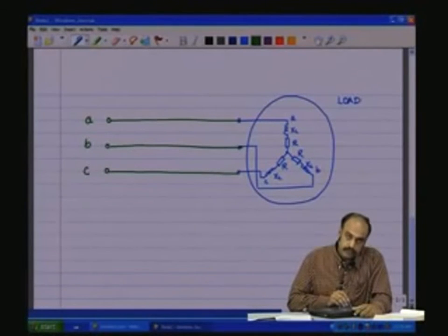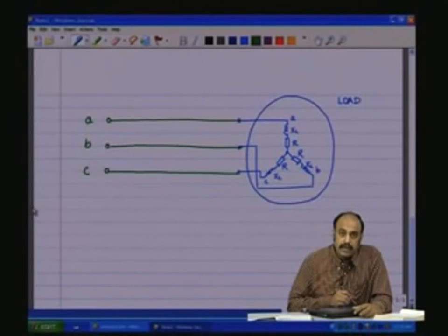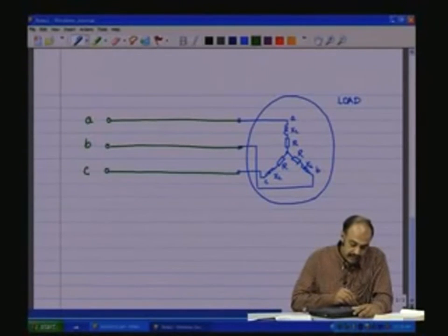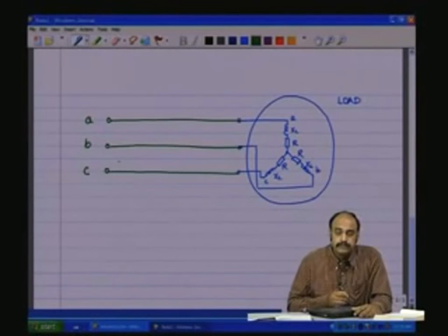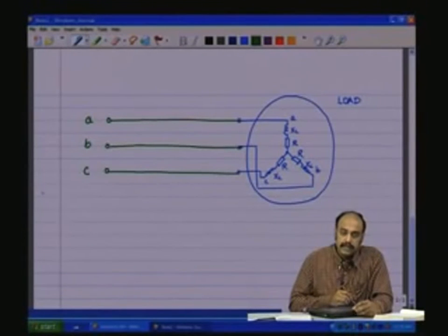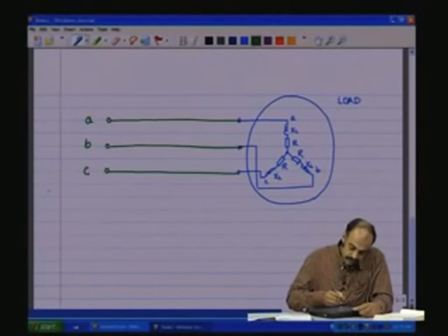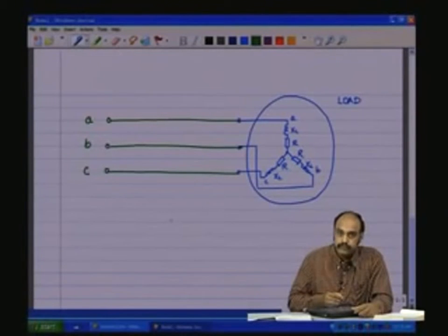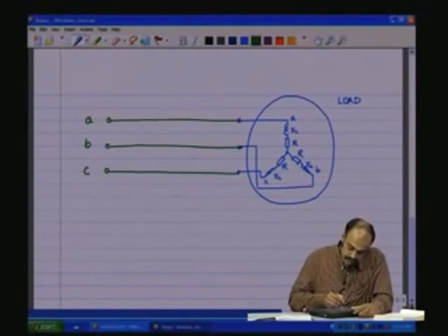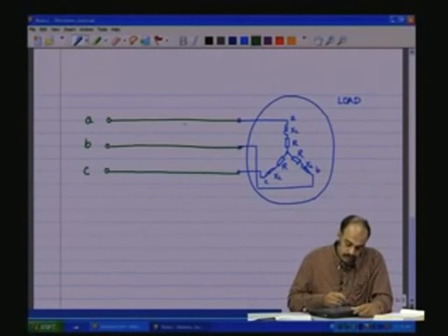In order to reduce the reactive currents drawn from the source side, so that the ratings of the source or the generator can be more optimally used, normally in the industry they try to improve the power factor from the line side by connecting a capacitive buffer in between, to act as a reactive generator.